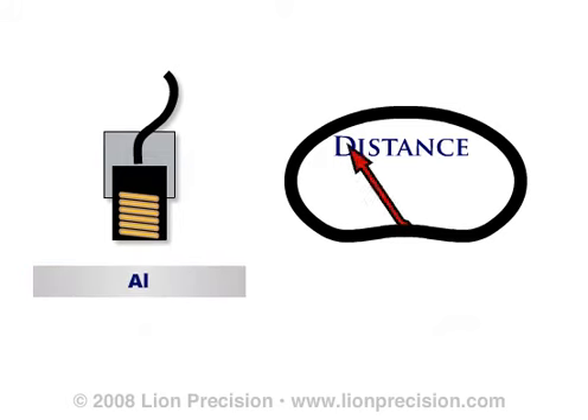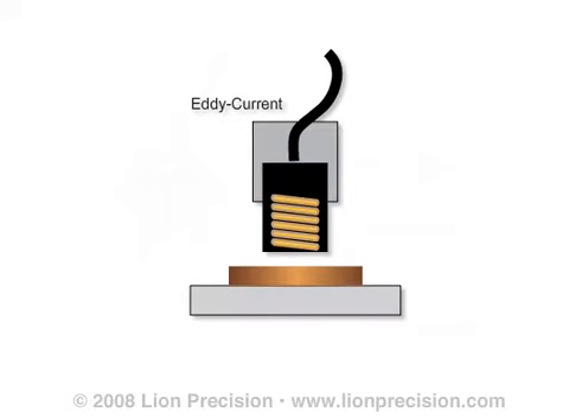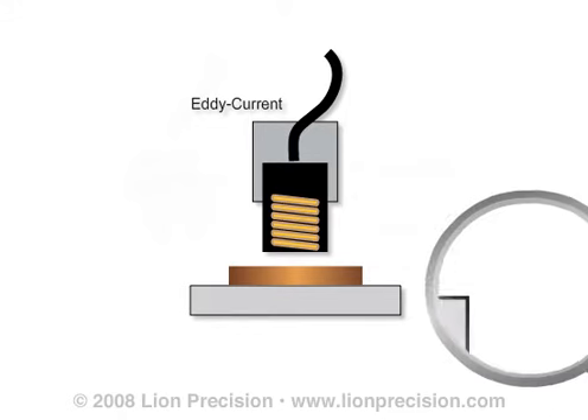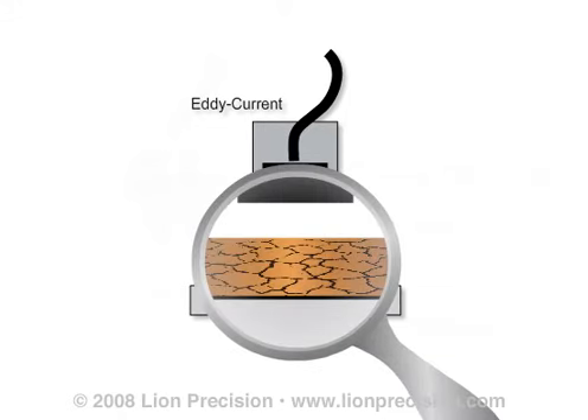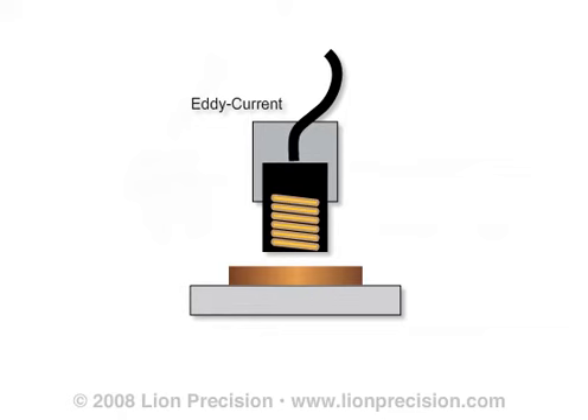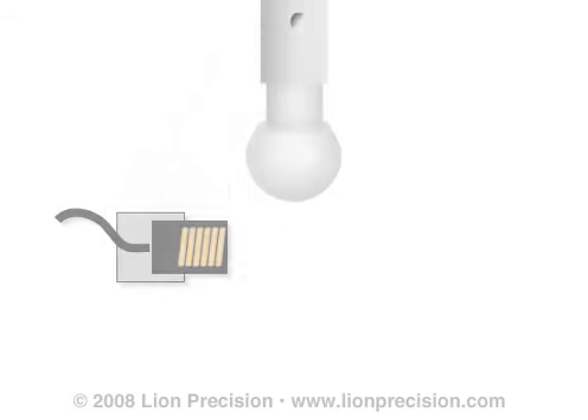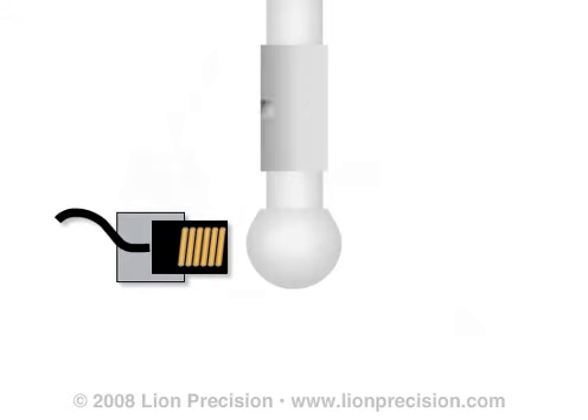When using eddy current sensors for precise measurements, it is critical that the sensor be calibrated for the specific material used in the application. The high permeability of magnetic materials, such as iron and steel, can also cause small eddy current sensor errors within the same piece of material. Within any imperfect material, there are microscopic cracks and material variations. The material's permeability changes slightly around these areas. While the changes are relatively small, the extremely high permeability of magnetic materials enables high-resolution eddy current sensors to detect these changes. This problem is most evident in rotating targets of magnetic materials.